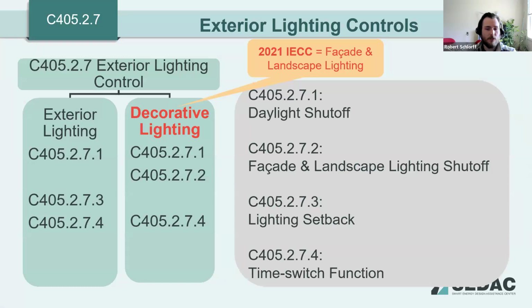Exterior lighting controls. There have been minor changes throughout this section. The primary change is that what used to be called decorative lighting is now called facade and landscape lighting. Other than that, the requirements are mostly the same. There are some general exceptions for all exterior lighting. These general exceptions are lighting for covered vehicle entrances and exits from buildings and parking structures where it's required for eye adaptation, and then lighting controlled from within dwelling units.